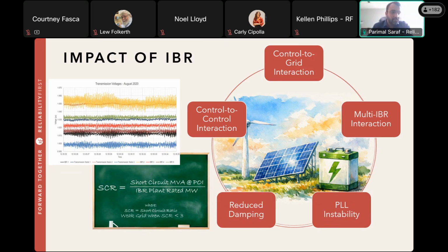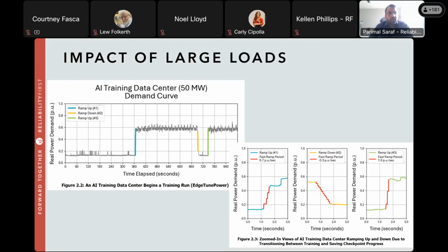So next slide, Courtney. So moving on to large loads, this snapshot on this slide is a capture of the training profile of an AI data center load rated at 50 megawatts. As has been seen in several data center profiles and also reported in the recently published NERC large load working group white papers, these AI data center loads tend to ramp up and down extremely quickly within a few seconds, ramping up and down between training and then saving checkpoint progress. And these ramp up, ramp down spikes can be several hundred megawatts in size within a few seconds.